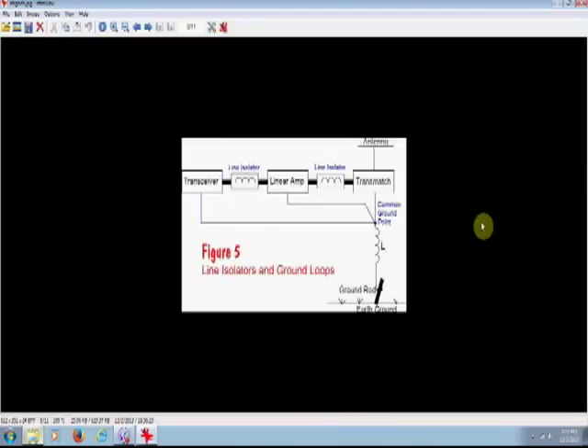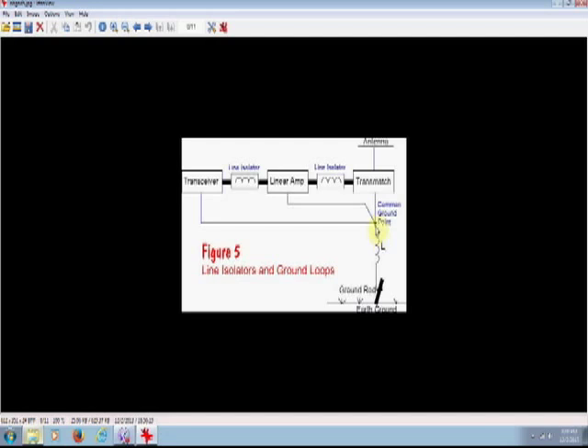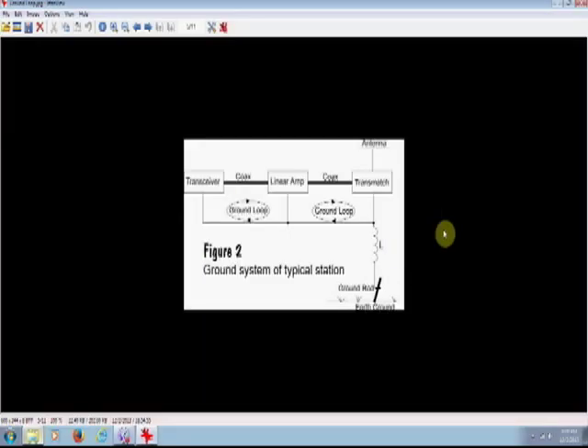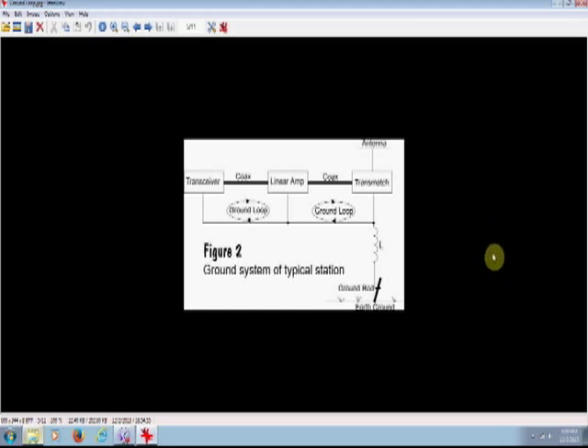So I hope that's helped you a little bit with grounding. And again I want to refer you to this chart. This is how your equipment should be grounded right behind the desk that you're operating on. Again, single point ground. All the ground braids or copper straps, they all go to one spot and then they go straight outside. They do not, they do not do this. Okay. Again, you'll have ground loops if you do it this way. All right, so with that said, the next one will be the ground rod part of it, which is outside out in the yard. And I'll go out there and take a few pictures.